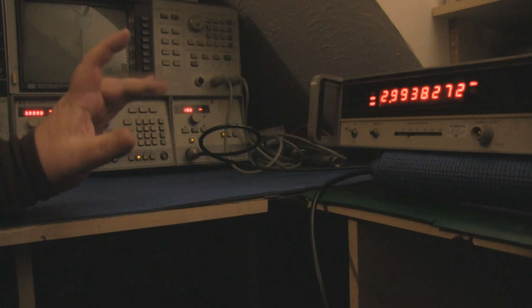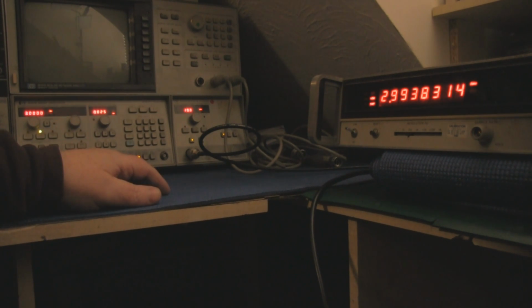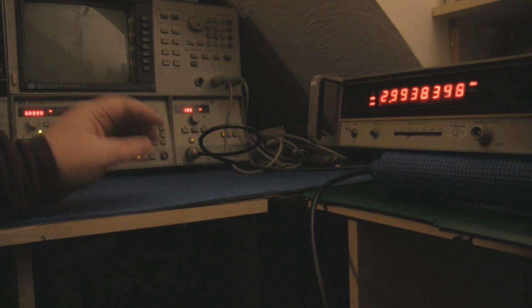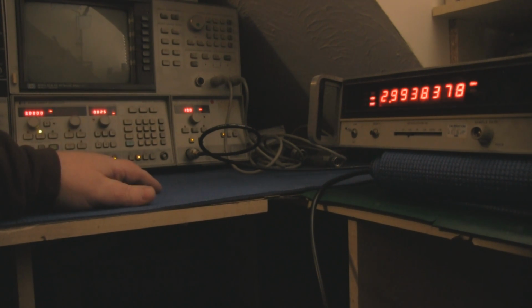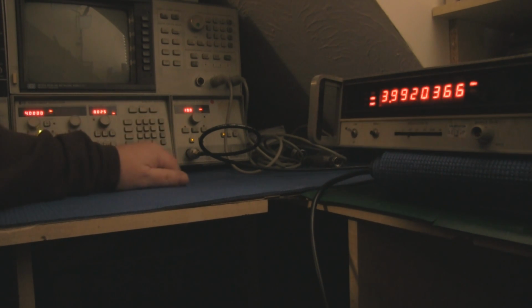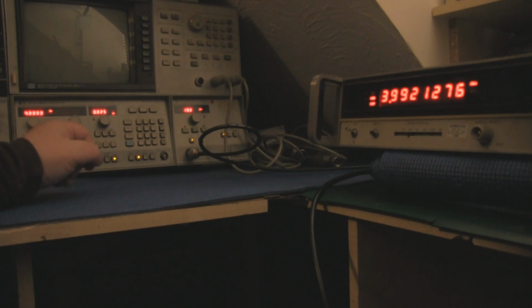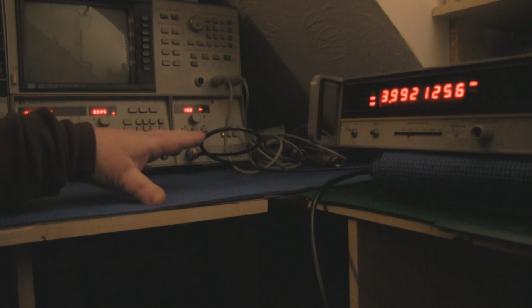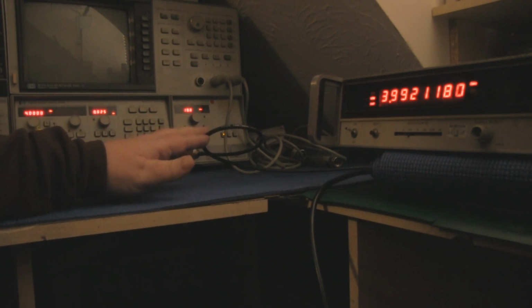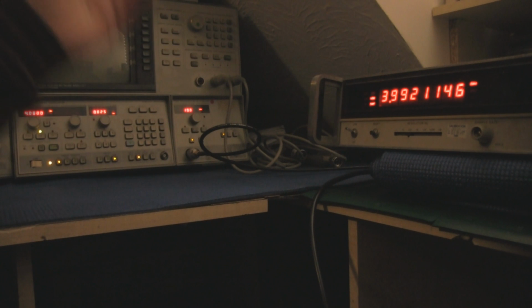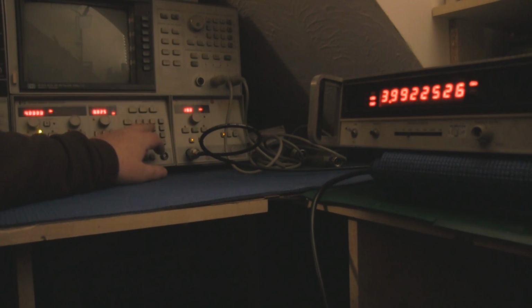Well, it seems to be getting better and more accurate as we go up the scale, because it's 2.993 GHz there, so it's definitely not out as much as it was at 1 GHz and 2 GHz, sorry. So it seems to be getting better as it goes up the scale. So let's try 4 GHz then, and again 3.992. I'm happy with that. A little bit of cable loss, you know, you can add 3 or 4 digits on at 4 GHz for the cable loss easily. So it is definitely getting more accurate the further up the scale we go. So let's try 5 GHz then. Yep, happy with that, and we'll go all the way up the scale now.